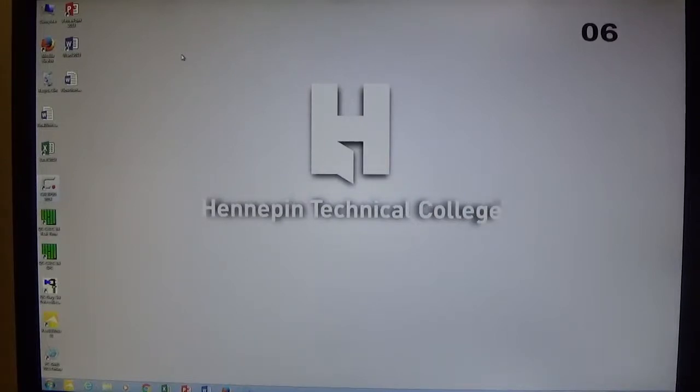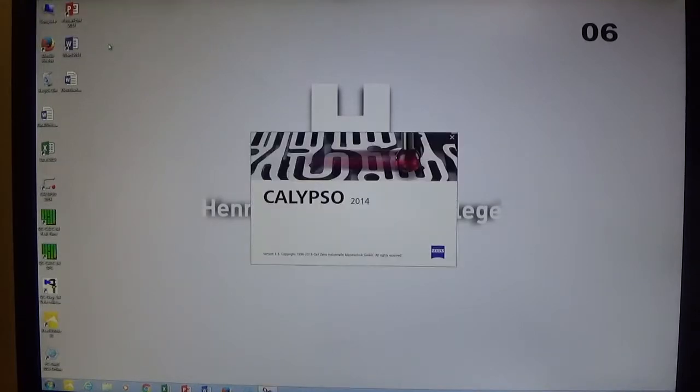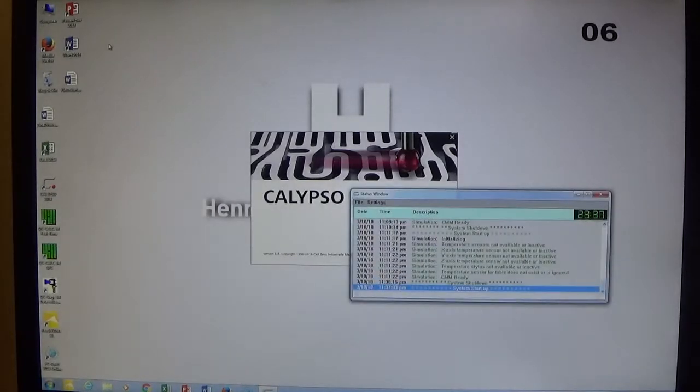This video is going to go through Calypso offline base alignment and stylus qualification. From the desktop we click on the Calypso 2014 icon and it goes through some startup menus. The first one is the login — there's no password so we just click OK, and then Calypso goes through some other startup windows until it gets to the main inspection page.